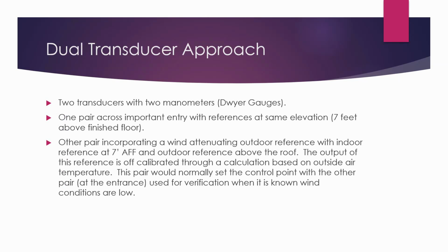We've got the outside air sensor at 7 feet above finished floor at the entry, and the interior sensor may not be near that entry, but it's at the same elevation. So this transducer is not affected by temperature. However, because the element is low at 7 feet, it is subject to wind stratification.